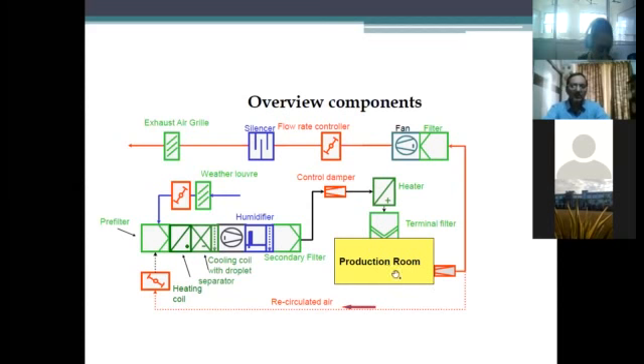This is a production room. From there, that air goes out through a filter, fan, rate controller, silencer, and exhaust regulator. But normally, if you are producing normal injectables, you do not throw out this air because it is costly, treated air. So on the bottom there's recirculated air, which comes out from the production room, goes back into the plenum, is again filtered and treated, and goes back into the production room. This is how recirculation is done.